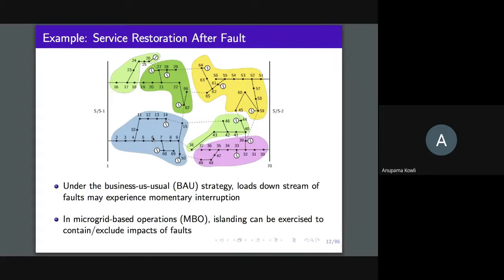So the other Matthew, you were saying what would happen if there was a fault here, at 5-6. That particular segment can be isolated, and before you isolate this, typically there's a momentary interruption. Usually there'll be a big circuit breaker here, and this entire feeder is going to get disconnected, de-energized for a while, and then 5-6 would be isolated with the help of isolating switches.